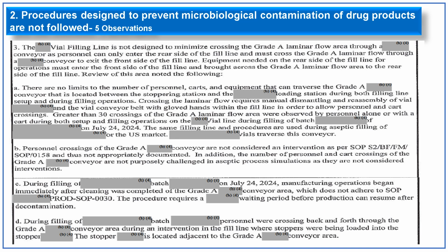The first of which is that there is no limit to the number of personnel, carts or equipment that can traverse the grade A conveyor located between the stoppering stations and the loading stations, both during the setup and the operation. Crossing the laminar requires manual disassembling and reassembling using gloves. It was observed that there were greater than 30 crossings of grade A laminar airflow by personnel alone or with a cart during the setup of the filling operations. This line was used for filling of the US market batches. Personnel crossing of the grade A conveyor is not considered an intervention and is not appropriately documented. The number of persons and carts crossing the grade A conveyor is not purposefully challenged in the aseptic process simulations.